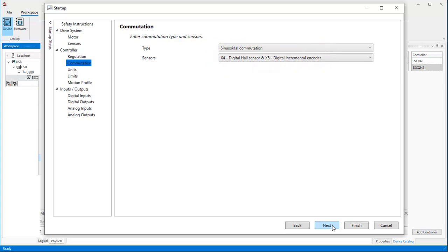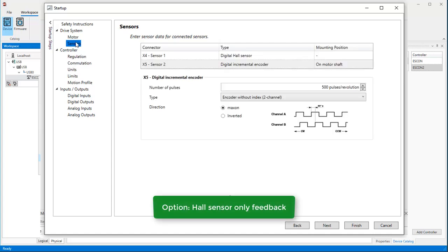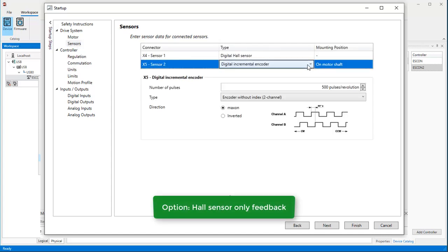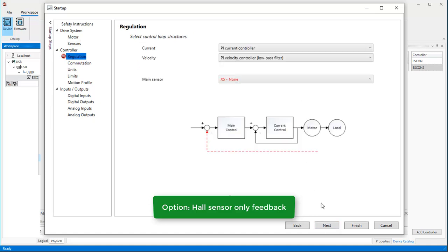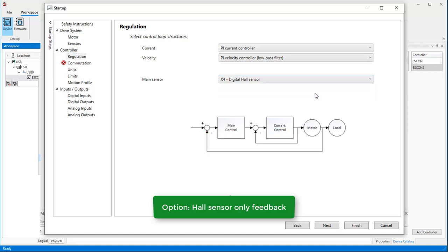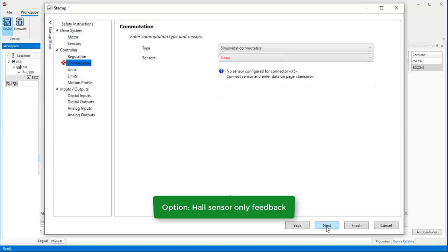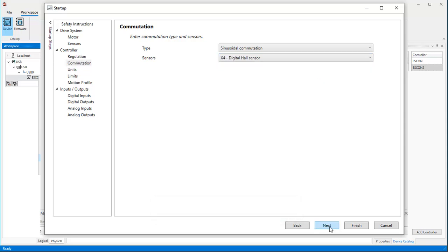By the way, brushless motors can also be operated with hall sensor feedback only, without encoder. Let me show you what would change in the basic setting in such a case. We jump back to the sensor definition and remove the encoder. The regulation must then be based on hall sensor feedback as well as the commutation. Press Next.